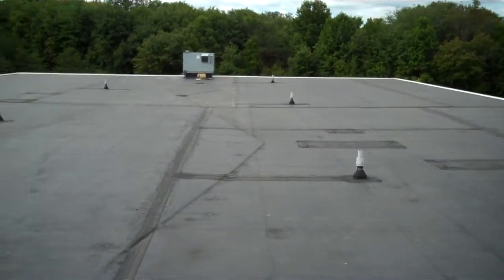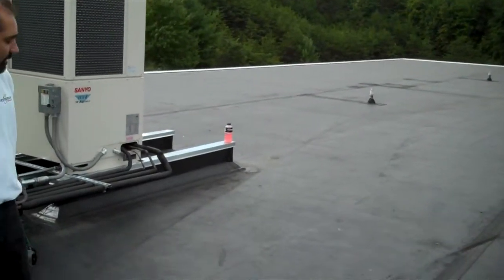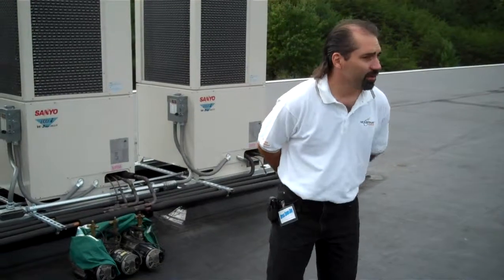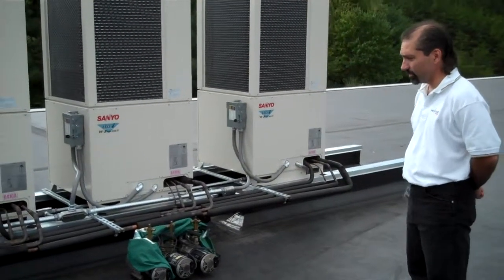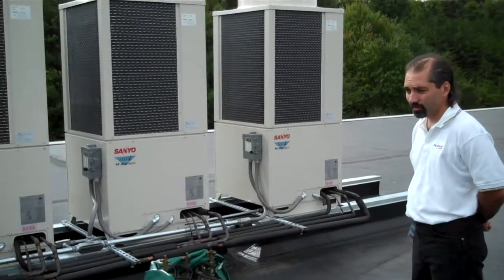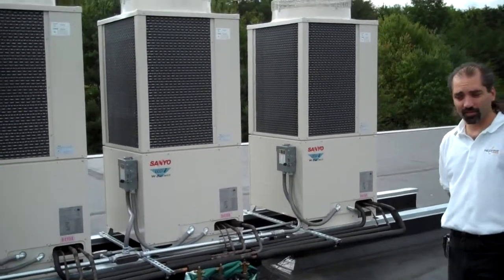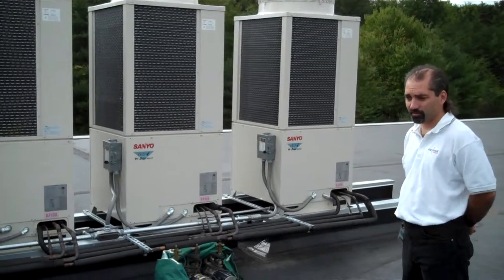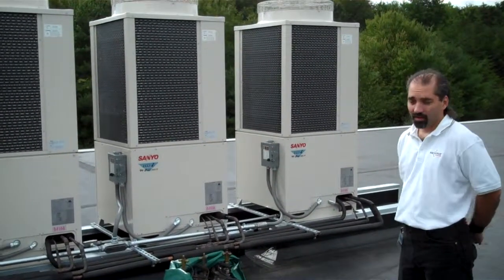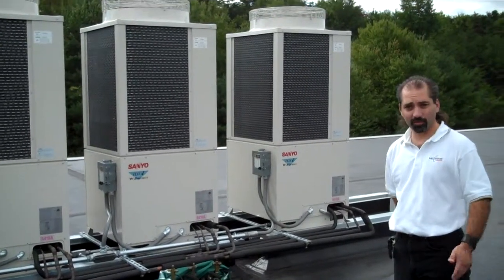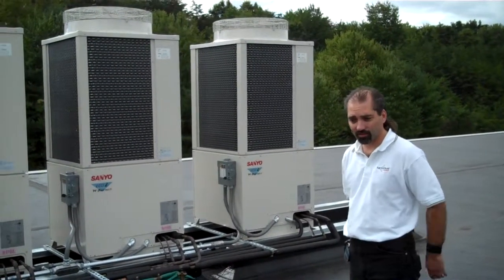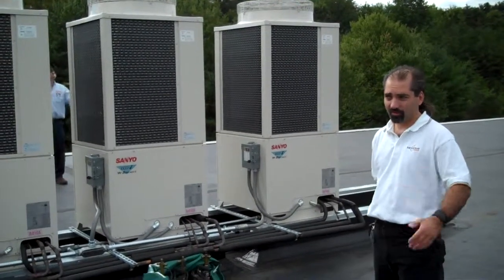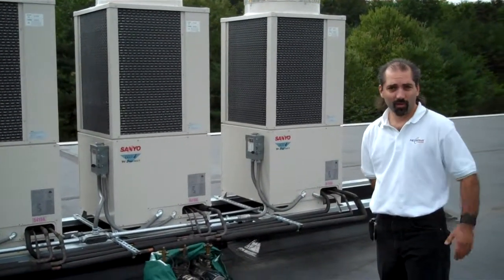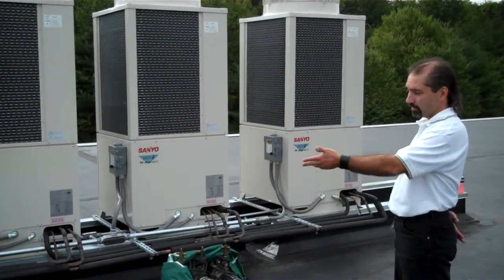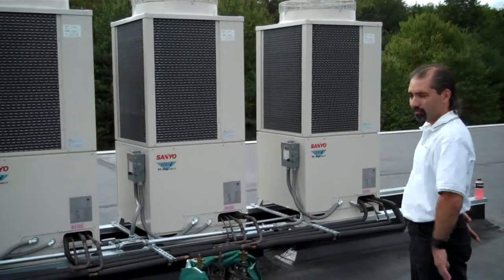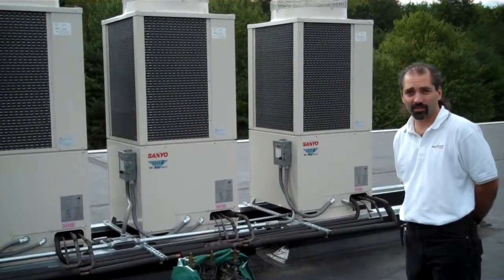So typically, wouldn't you see a lot of rooftop units with a lot of place for water leakage or rain to come down through? Absolutely. The original quote that another contractor had done for them had figured on doing multiple split systems, typically residential type split systems with air handlers for the classrooms, condensing units on top of the roof here. Served in multiple penetrations for all those refrigerant line sets, all the electrical for the condensing units going down through the roof to each classroom. There probably would have been 20 condensing units up here on this roof, plus 20 roof penetrations. We were able to do it with 2 penetrations for the line sets, 1 roof curb for each energy recovery system. So we essentially made 4 penetrations versus 20.